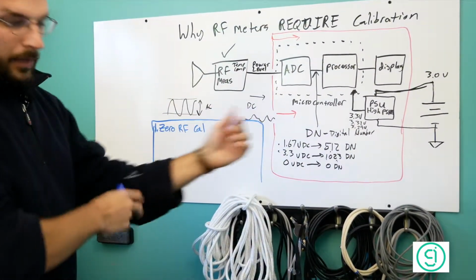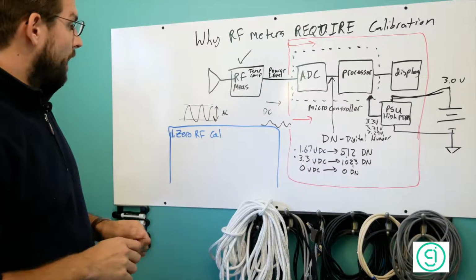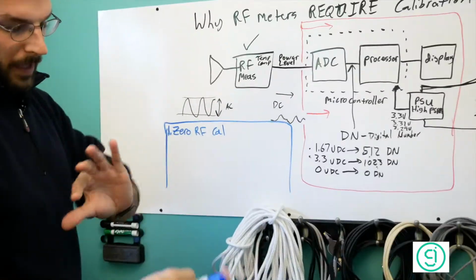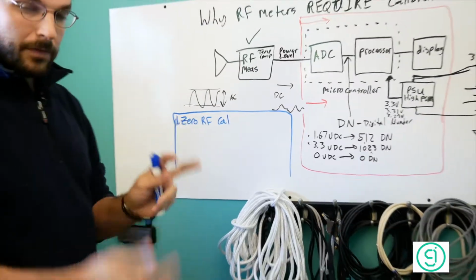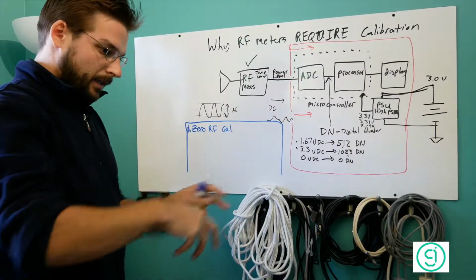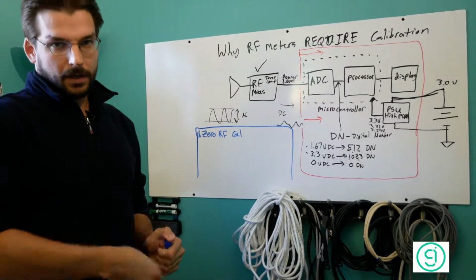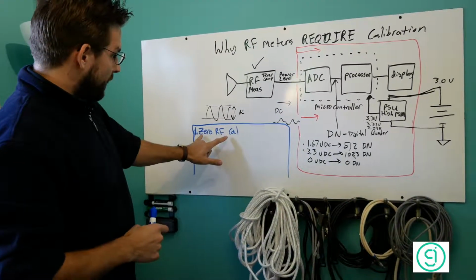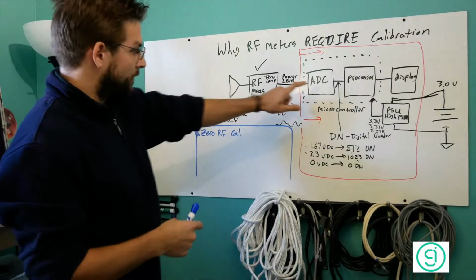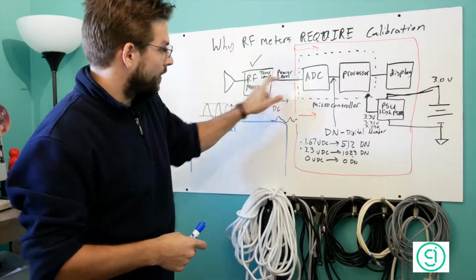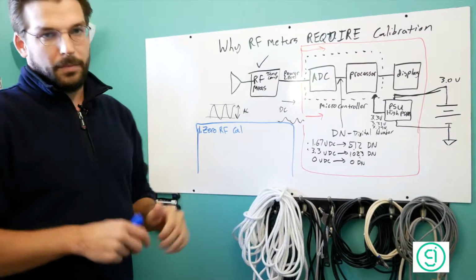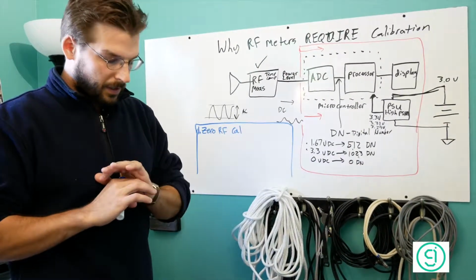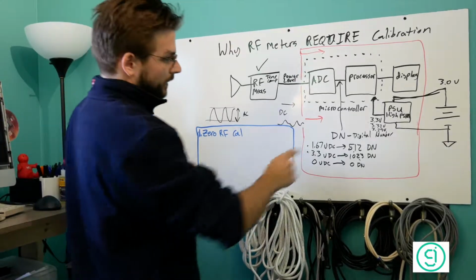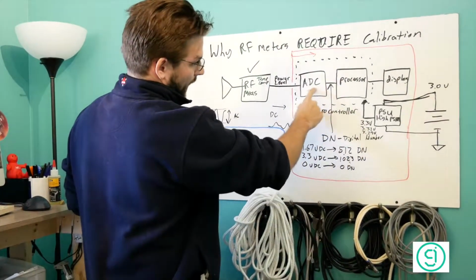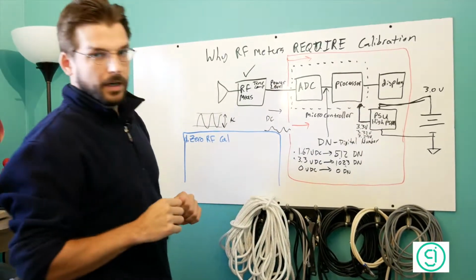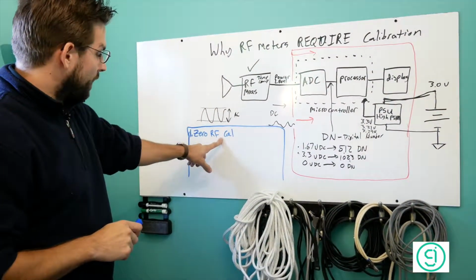We have an RF quiet environment downstairs on the assembly line. We have a metal shielded enclosure in that RF quiet environment. We put the entire device in that enclosure, close the lid. We have a software subroutine that takes a bunch of analog to digital converted samples from our RF amp and establishes a baseline for when there's 0 RF, when it's in a totally quiet environment. What is the digital number that comes out of the analog to digital converter in that environment? So that gives us 0 RF cal.